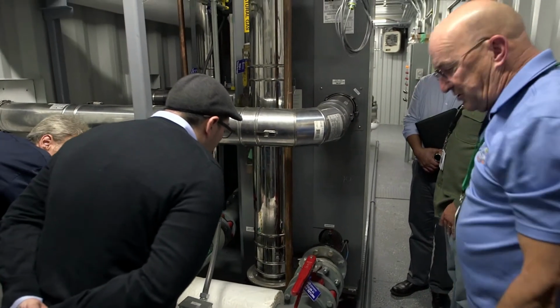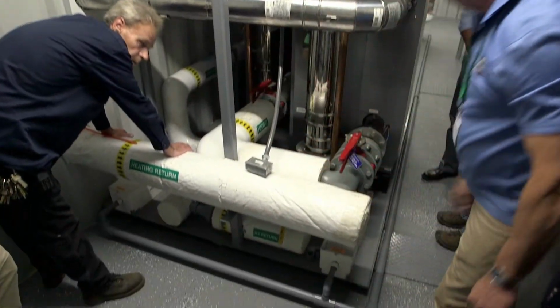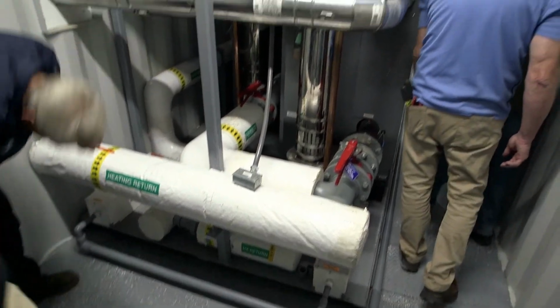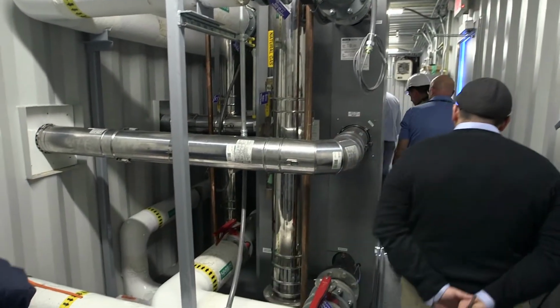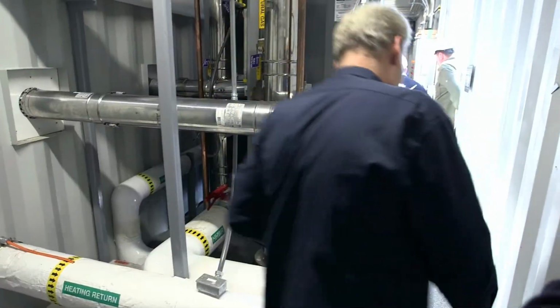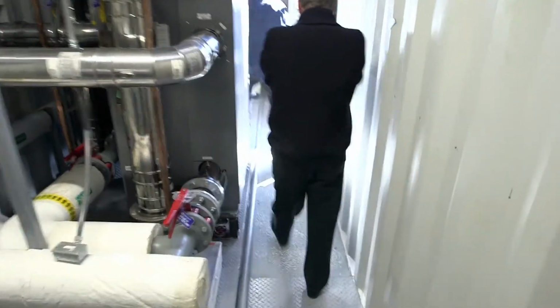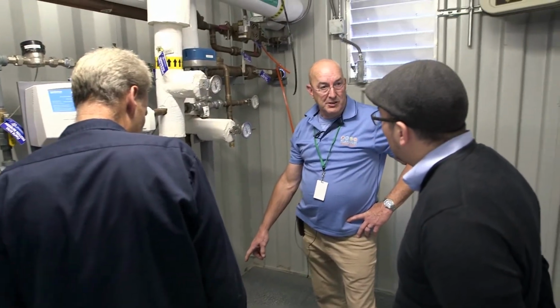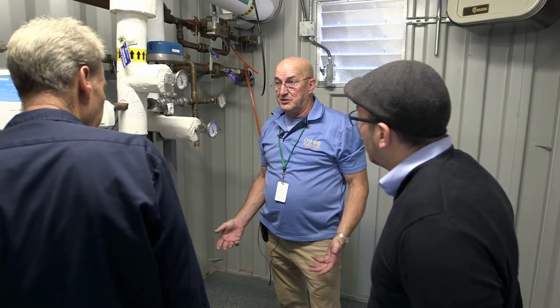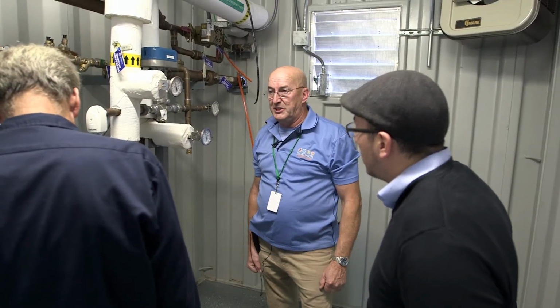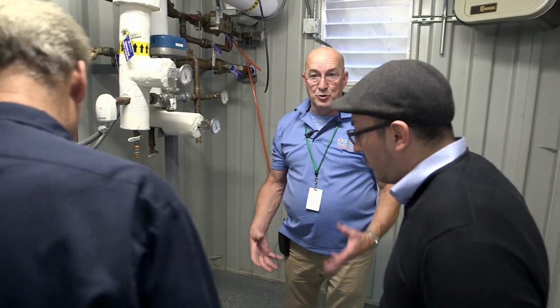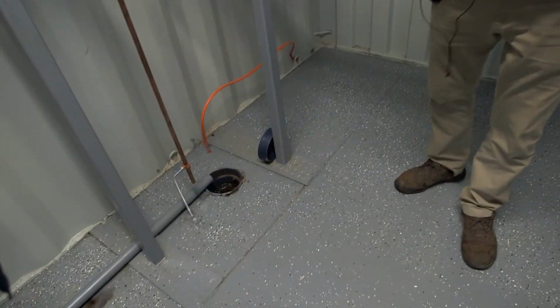But the easiest way to check that, as you can see, these lines all go into this gray line, okay? You walk along, and you follow the gray line, okay? See it dripping now? Okay? It's telling you that those drains are clear and they're working. You're always going to have water coming into this drain because that's what makes these boilers efficient, is they're condensing boilers. They suck every last bit of heat out that they can. All right? And that causes the gas to condense. Whatever's left, it condenses and it comes out here.